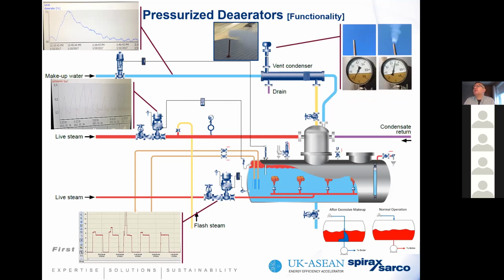However, look at even the vent. In this case example, you can see this customer is that each time they filled water into the deaerator, the pressure dropped off significantly because they were surge filling cold water, be it 20 degrees, to the deaerator, which had the impact of dousing the water temperature and pressure. And you can see in this case is that the deaerator became sub-atmospheric. So when they were filling water, instead of venting excess oxygen, they were drawing oxygen into the system, which was further impacting on the oxygen content of the feed water.